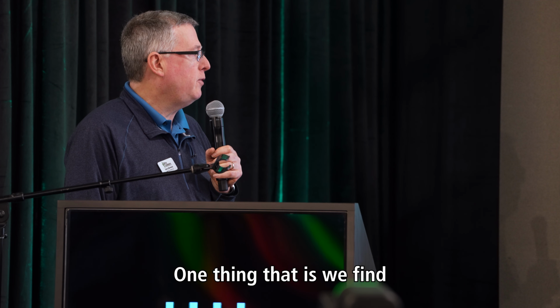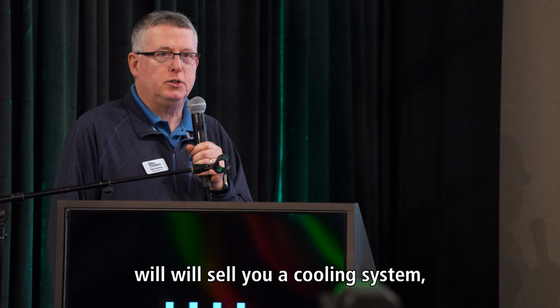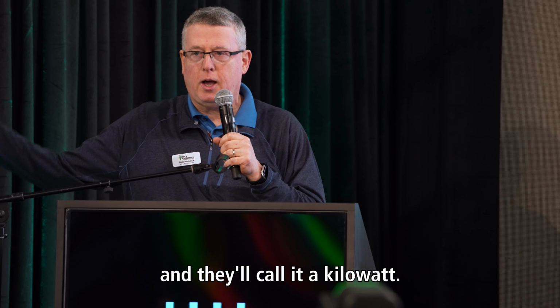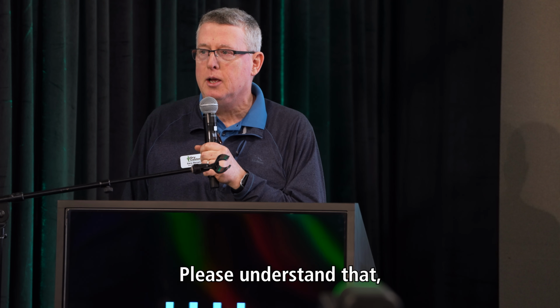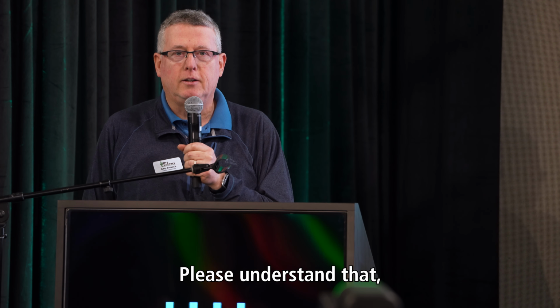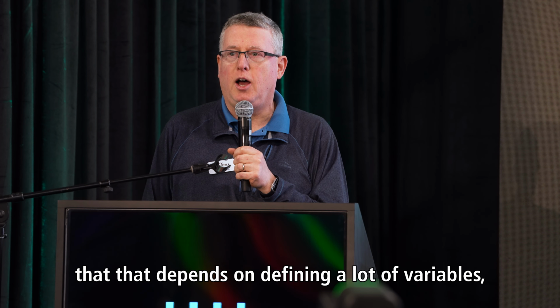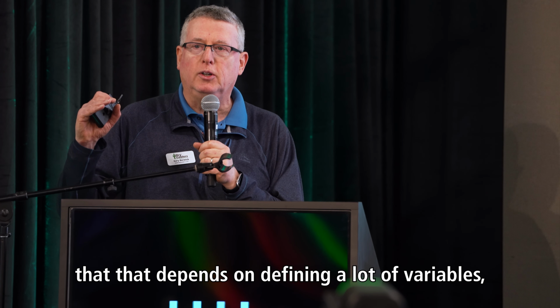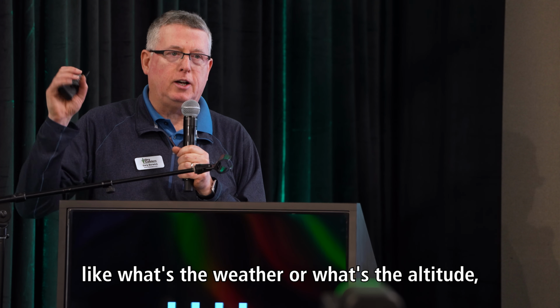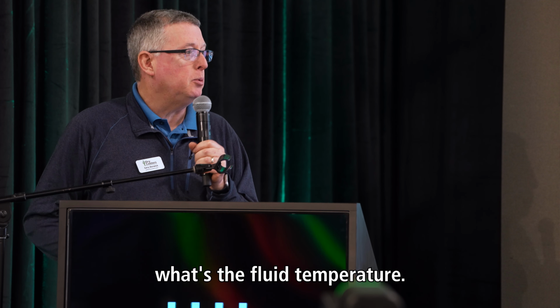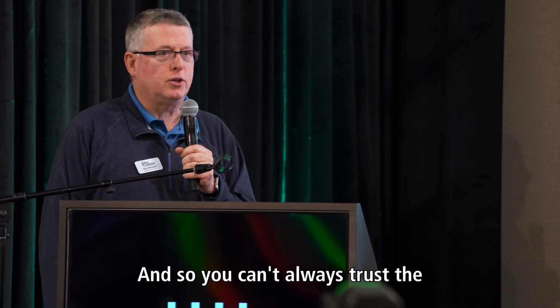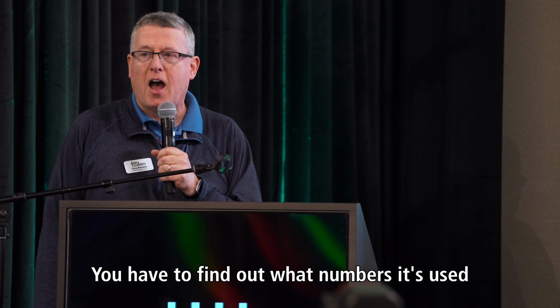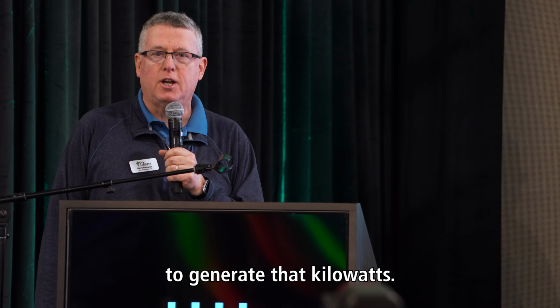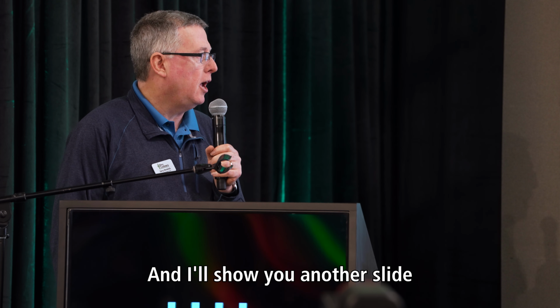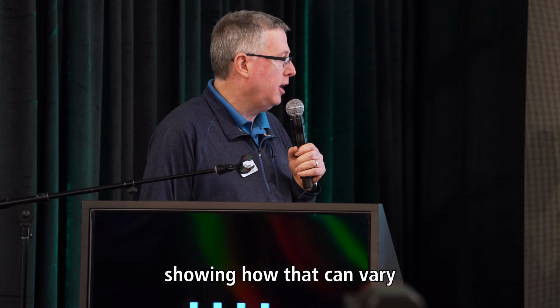One thing we find interesting is a lot of people will sell you a cooling system and call it, say, a 200 kilowatt cooler. Please understand that depends on defining a lot of variables, like the weather, the altitude, the fluid temperature, so you can't always trust the label on the cooler. You have to find out what numbers it's using to generate that kilowatt rating. I'll show you another slide showing how that can vary.